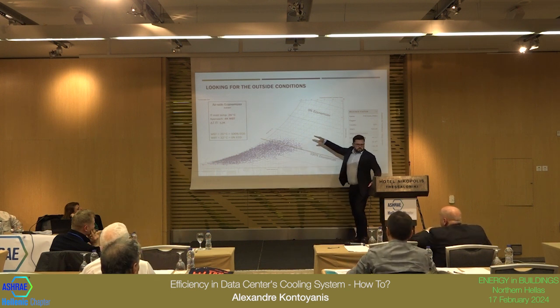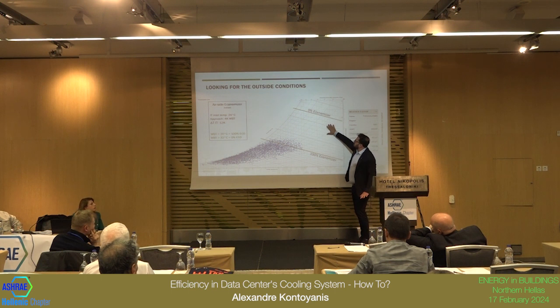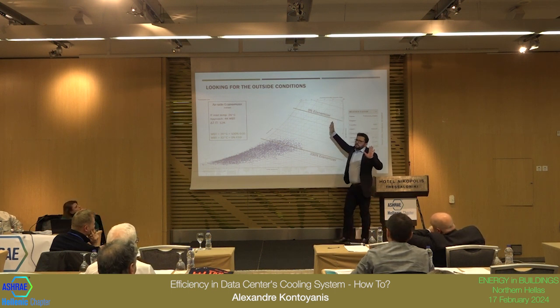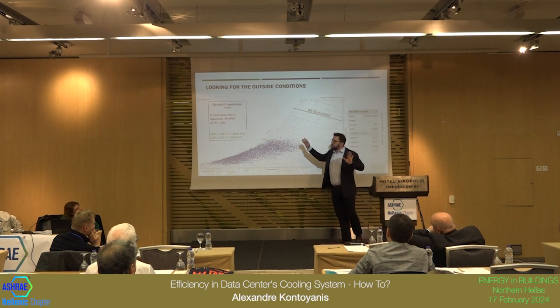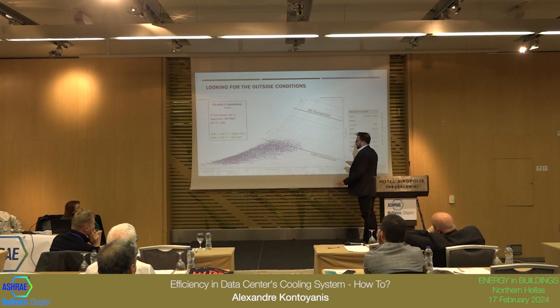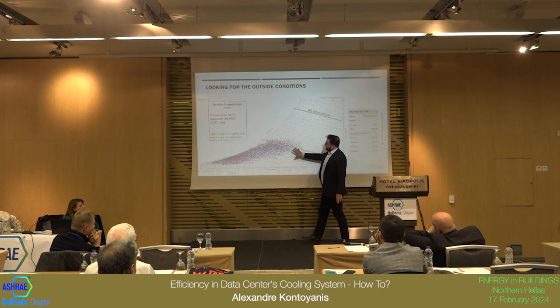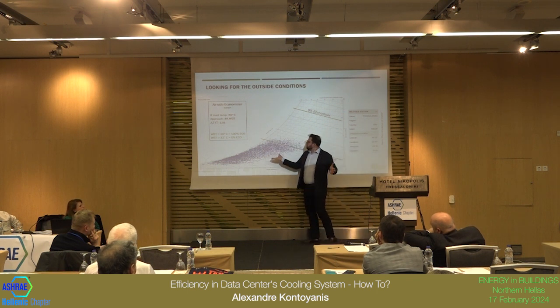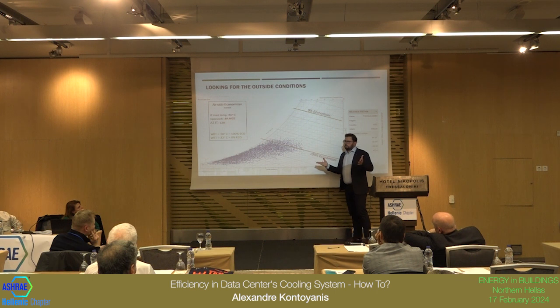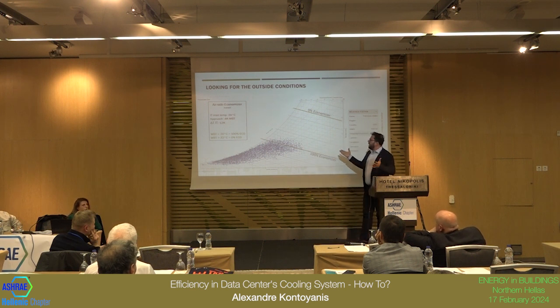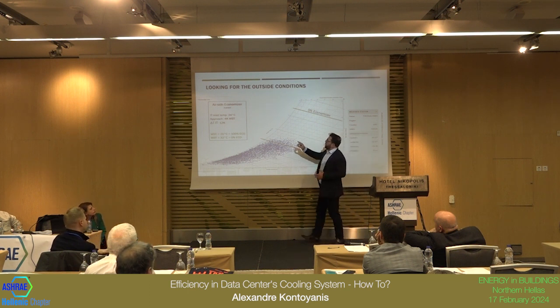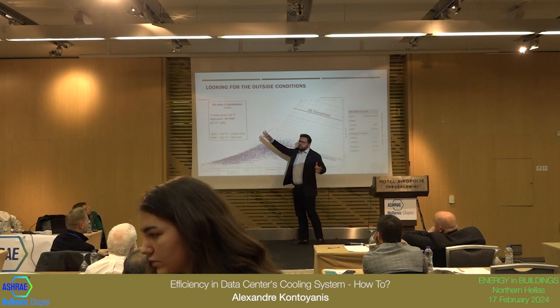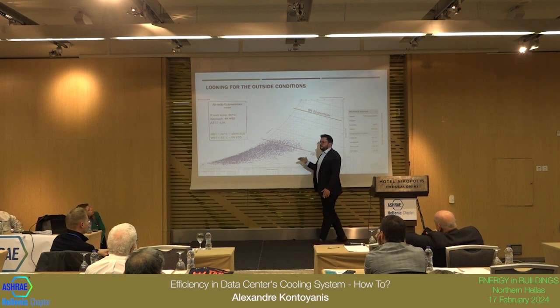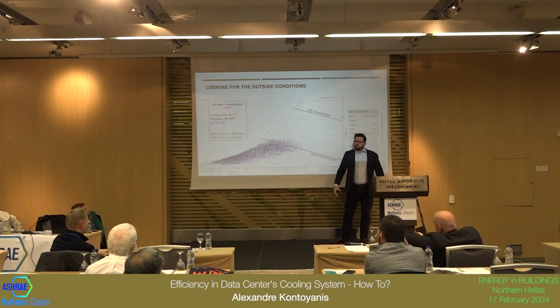From this line to this upper line, we can do it partially. Above this line, we cannot. We need to run chillers. I did not calculate it, but below this line is around 80% of the time, 80.5 or 85.9. So what I'm saying is, in Thessaloniki, if you want to run your data center at 24 degrees, which is a pretty common temperature, you could run without chillers 80% of the year.